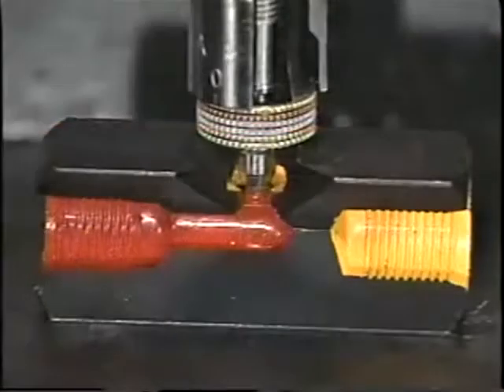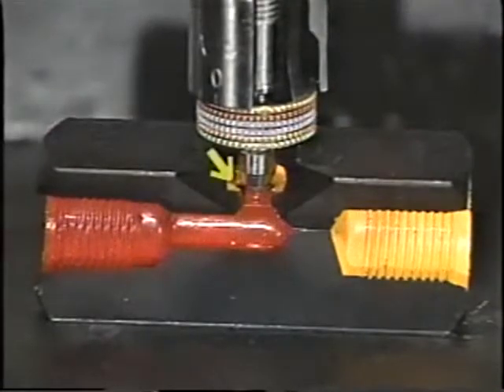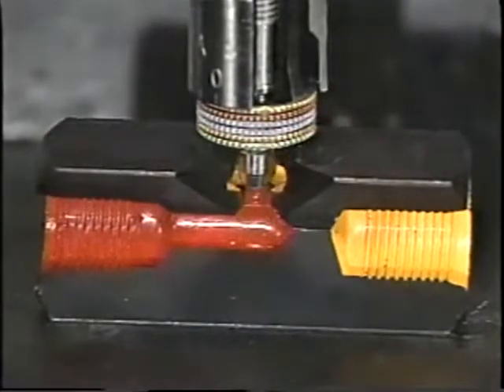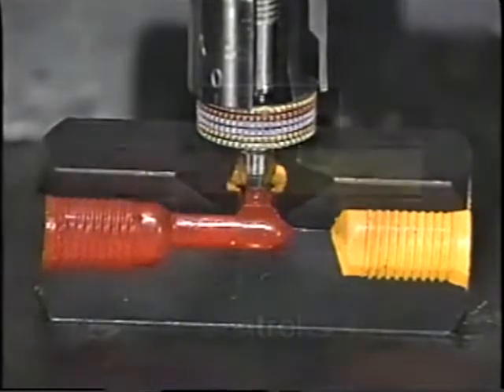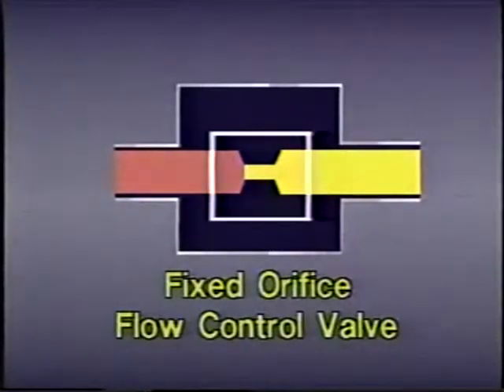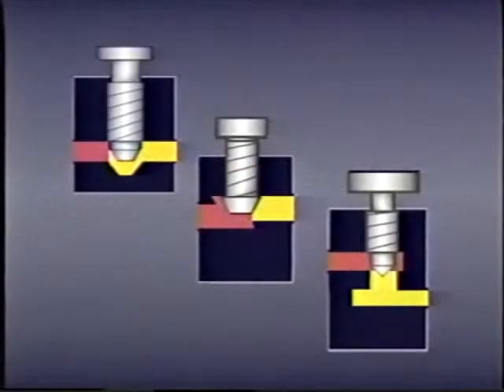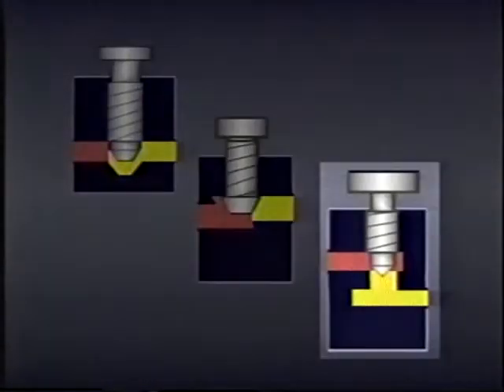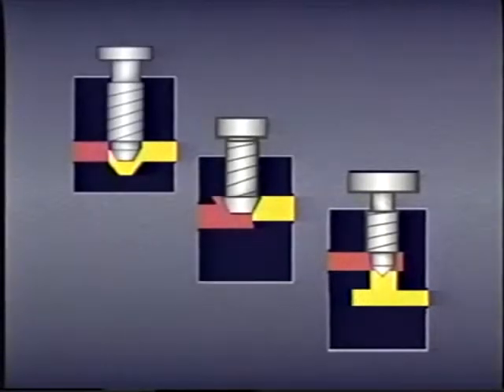The orifice is the restriction in the cross-sectional area in the flow control valve. The larger the orifice, the more fluid can flow through it. In some flow control valves, the size of the orifice is fixed and cannot be changed. However, many systems require that the size of the orifice be adjustable. Gate valves, globe valves, and needle valves are all examples of variable orifices.